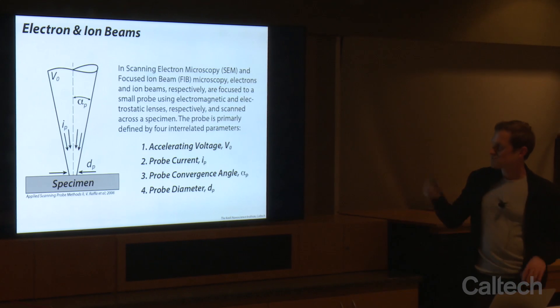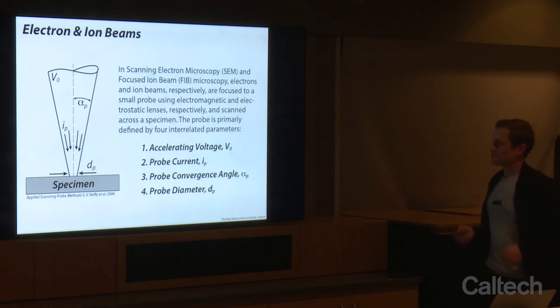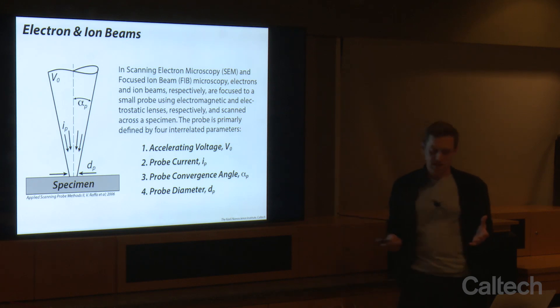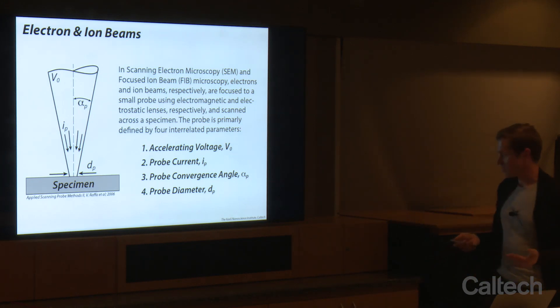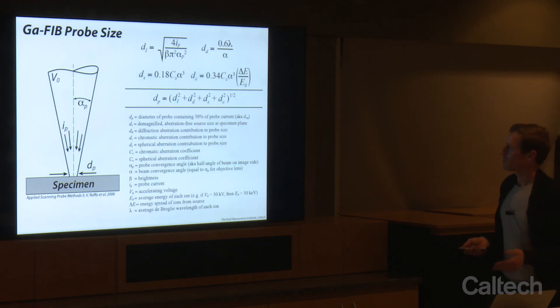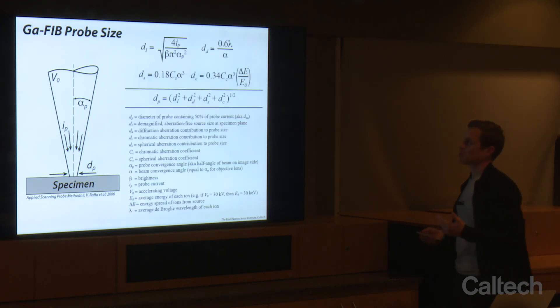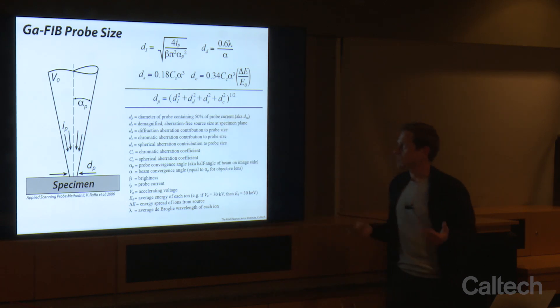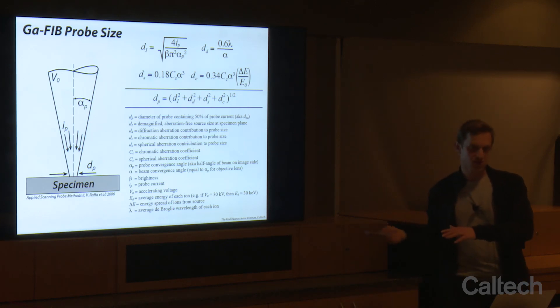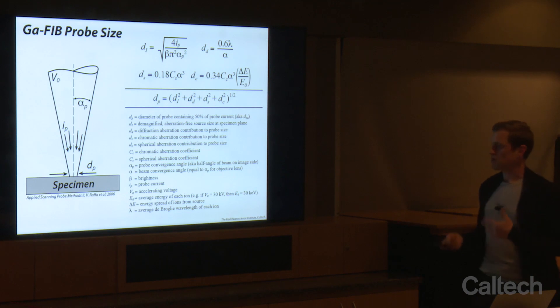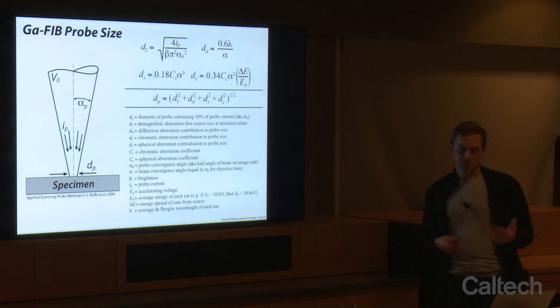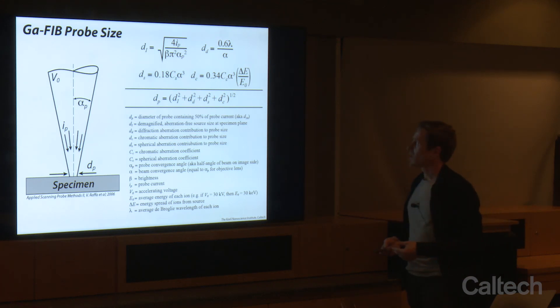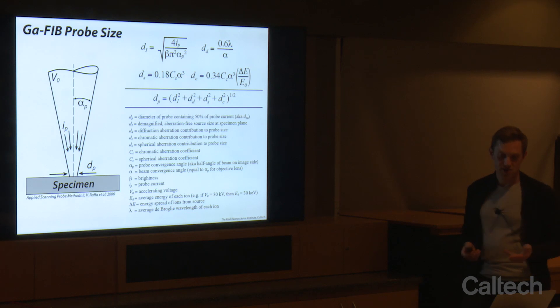This is true for both electron beams and ion beams: the main parameters are the accelerating voltage, the probe current, and the probe convergence angle. These come together to give us a probe diameter for our beam. We can look at the relevant equations for the gallium-focused ion beam and all the definitions. As we do our microscopy, we don't typically make a lot of these calculations, but it's good to know these equations exist to understand why we're getting certain probe sizes and how they relate to aberrations and the main parameters — voltage, current, and convergence angle.